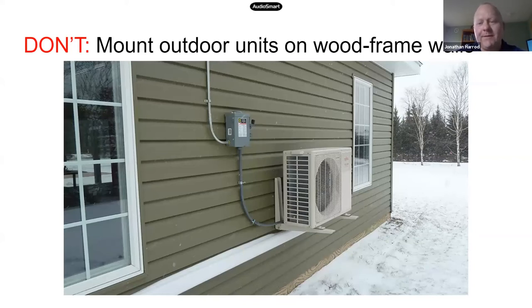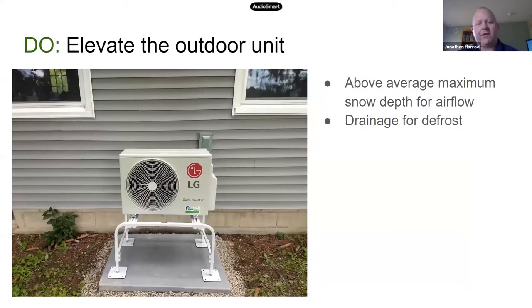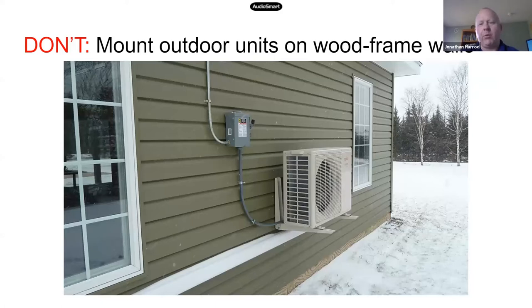This is something we did once and we will never do again. You don't want to mount the outdoor unit on a wood frame wall. One of the ways that these systems get their efficiency is that they have variable speed compressors and fans. And so in order to match the heat load of the house as they're modulating, they will ramp up that compressor and that fan over a range of frequencies that might range, for the compressor, from about 10 cycles per second up to about 120 cycles per second. And somewhere in that range of frequencies is a frequency at which that siding is going to start to vibrate and you're going to get noise complaints. So we really, whenever possible, prefer to mount the unit on the ground like you see here, or if we need to attach it to a wall, we want to attach it to a masonry foundation wall.